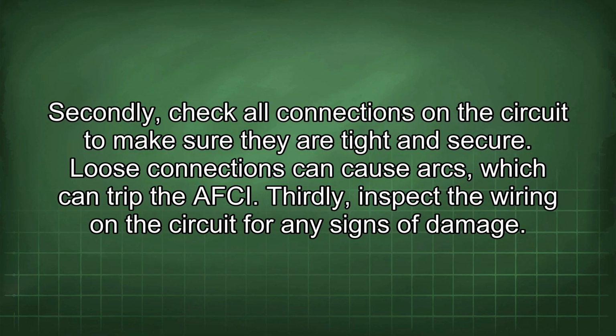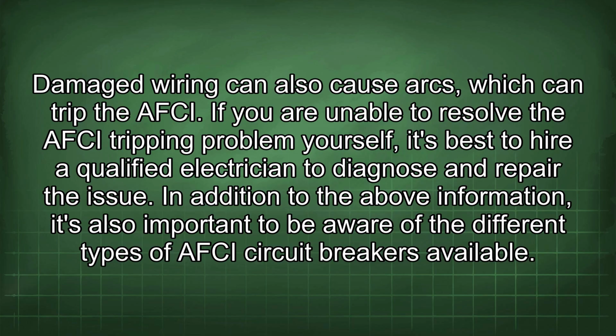Secondly, check all connections in the circuit to make sure they're tight and secure. Loose connections can cause arcs, which can trip the AFCI. Thirdly, inspect the wiring on the circuit for any signs of damage. Damaged wiring can also cause arcs, which can trip the AFCI. If you are unable to resolve the AFCI tripping problem yourself, it's best to hire a qualified electrician to diagnose and repair the issue.